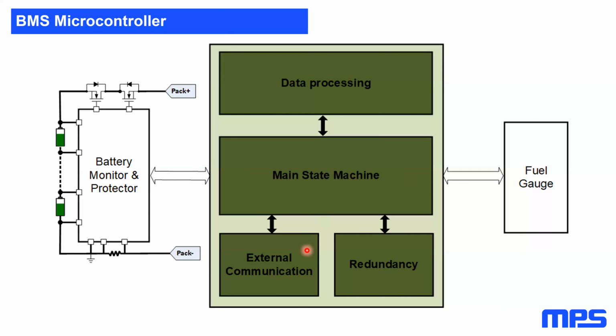Finally, some redundancy safety checks are usually performed after data processing within the MCU. It can be programmed to double-check possible overvoltage, undervoltage, or any fault, in case the battery monitor was not able to detect them properly. This good practice also helps to detect if the battery monitor is properly working, increasing the safety level of the complete BMS.